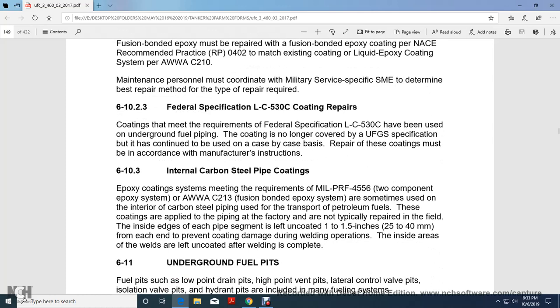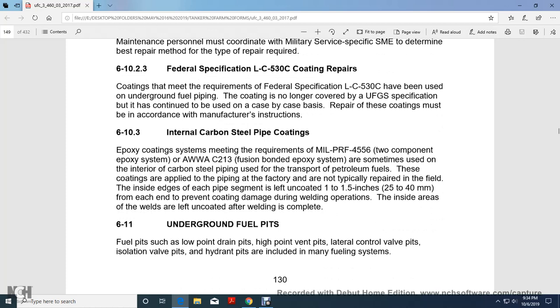6-10.2.3, Federal Specification LC530C for coating repairs. Coatings meeting Federal Specification LC530C have been used in the underground fuel pipe. The coating is no longer covered in the Unified Guideline specification, but continues to be used on a case basis. Repair of these coatings must be in accordance with the manufacturer's instructions.